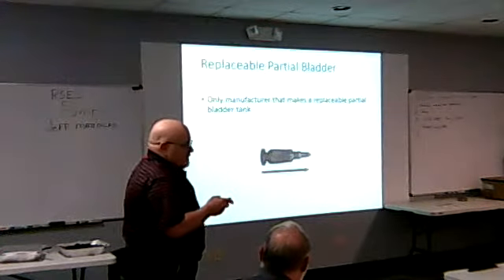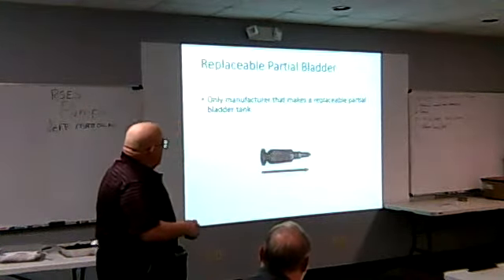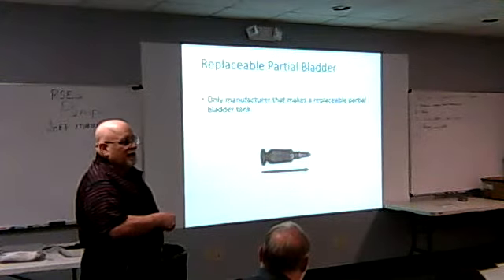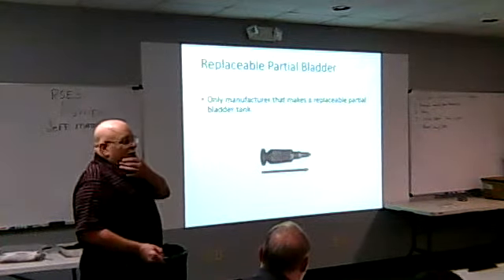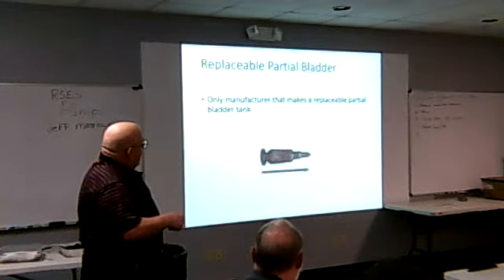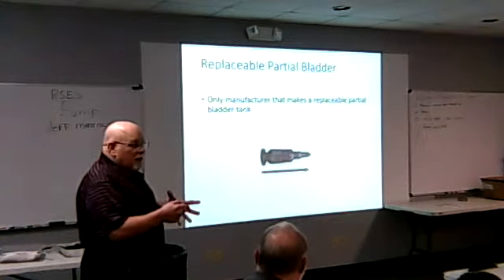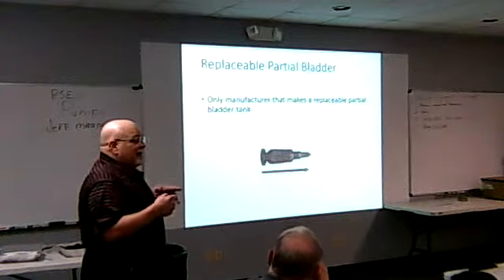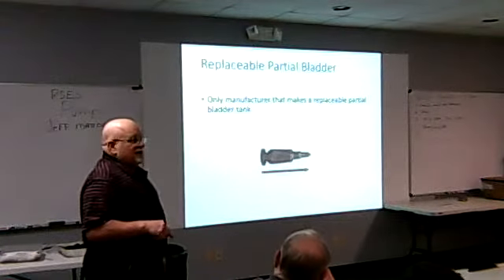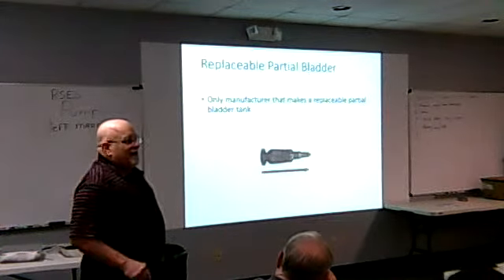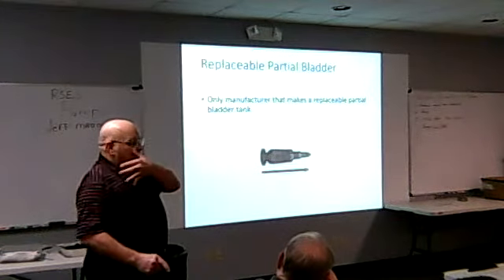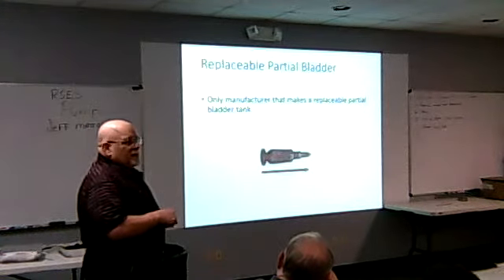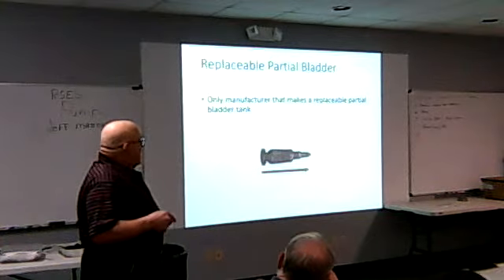This is a partial expansion. This is the bladder that's in a CAX tank or a CBX tank. Everybody makes the same thing, Armstrong, anybody. There's a big tank. This is your bladder I was talking about, much smaller. When we size the system, it'll say, I need 22 gallons of acceptance and I need a 67-gallon tank to make that selection. It tells us we know what our expanded volume is. I can't exceed that.